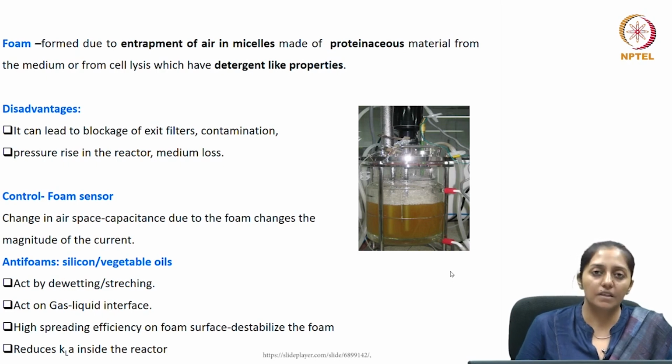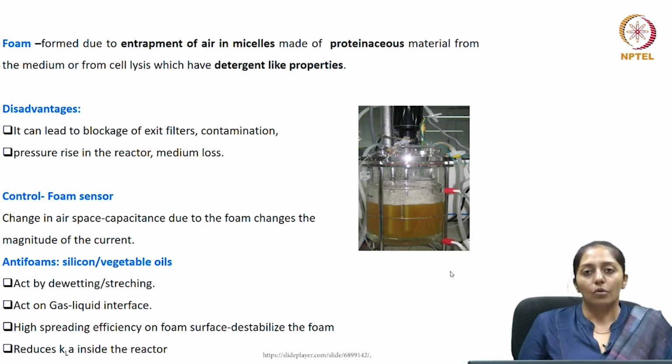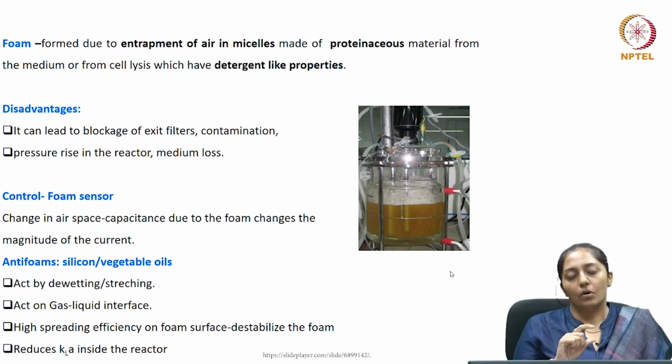Now, the disadvantage is that it can lead to blockage of the exit filters and thereby contamination. And because of the blockage of the exit filters, it can eventually lead to pressure rise inside the reactor, which can be dangerous. So, to control foaming inside the reactor, there is an anti-foam probe which is based on air capacitance.